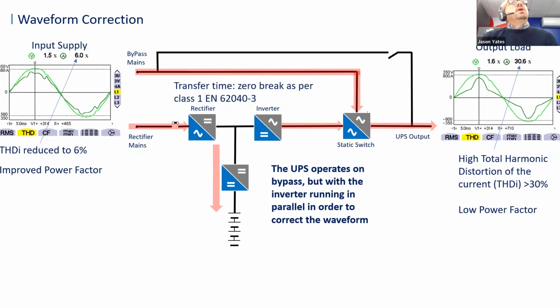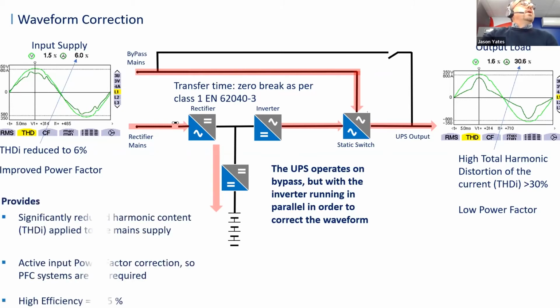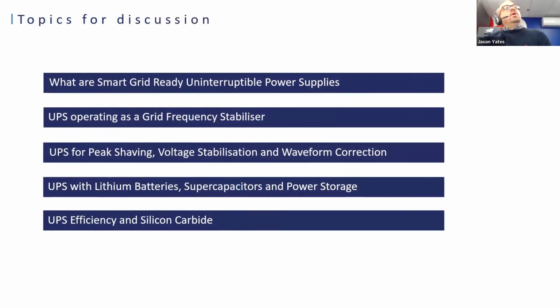One of the key benefits is that it's still a UPS, so it can still provide full battery backup with zero breaks. So in the event of a mains failure, it could still provide full battery backup, and then once the main supply has returned, go back to waveform correction mode. Benefits of this: it can significantly reduce the harmonic content being applied onto the main supply. It's an active input power factor corrector, so you don't need any power factor correction systems. And in this mode, because it's operating in bypass, it can run highly efficiently at 98.5% efficiency. So those are just a few of the smart grid-ready applications that we can use UPS for.